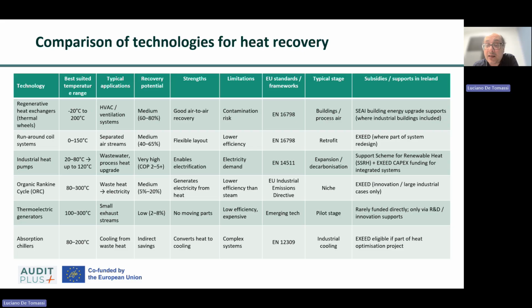Organic Rankine cycle systems convert waste heat into electricity using an organic working fluid instead of water and steam. They are most effective for waste heat sources between approximately 80 and 300 Celsius degrees and are commonly found in cement, glass, biomass, and industrial manufacturing sectors. ORC systems typically convert 5 to 20% of available waste heat into electricity.